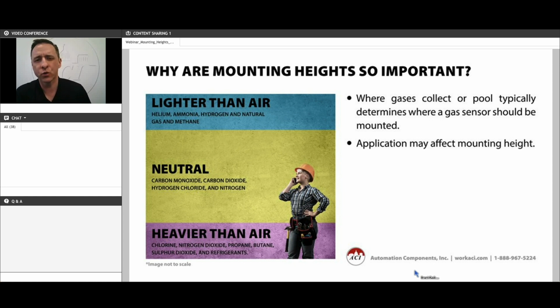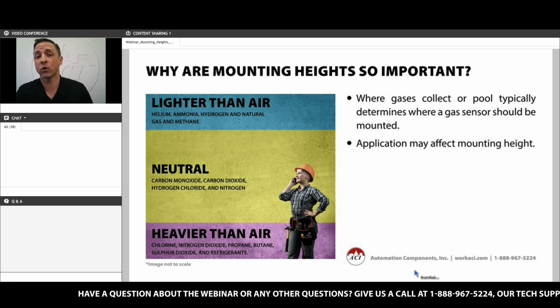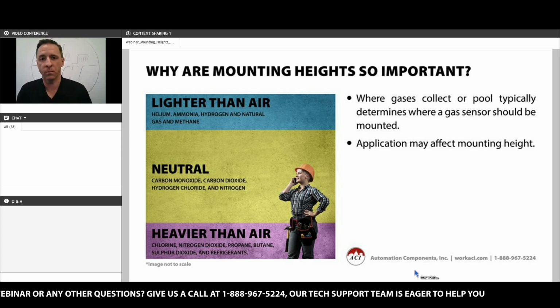Some gases are more or less neutral to the ambient air, like carbon monoxide, carbon dioxide, nitrogen, and hydrogen chloride. For those gases, we will recommend mounting in what we call the breathing zone, which is 4 to 6 feet from the floor. And then the heavier than air gases like chlorine, nitrogen dioxide, propane, butane, and pretty much all types of freon refrigerants are heavier than the ambient air, so they will sink to the floor. For those gases, we would recommend mounting as close to the floor as possible, anywhere from 6 to 18 inches above the floor. That's the general recommendation. We look at the specific density of the gas, because in any certain space, that gas will either rise to the ceiling, sink to the floor, or be more or less neutral to the ambient air. So in most applications, that's where we're going to recommend mounting the sensor, specifically based on the chemical weight or density of that gas.